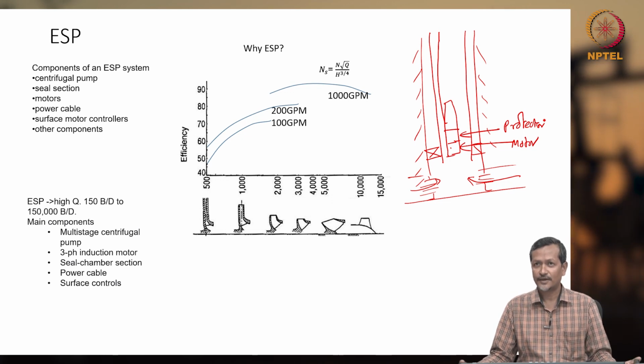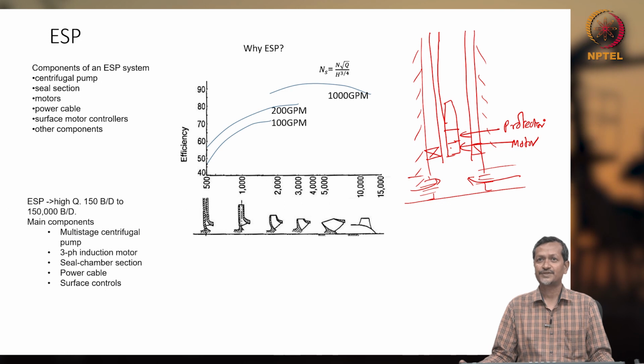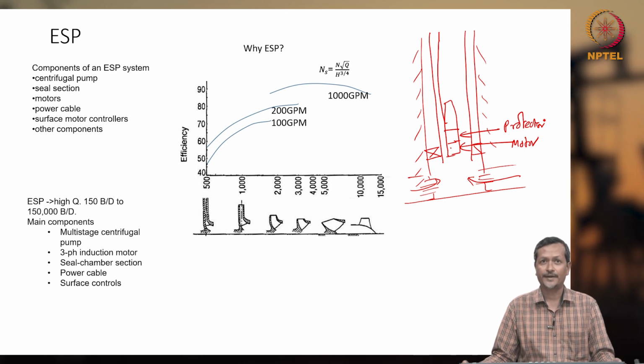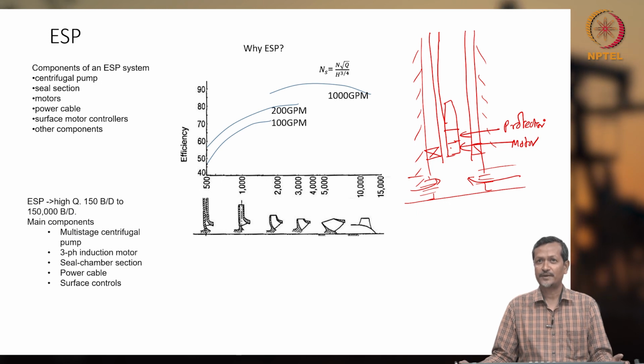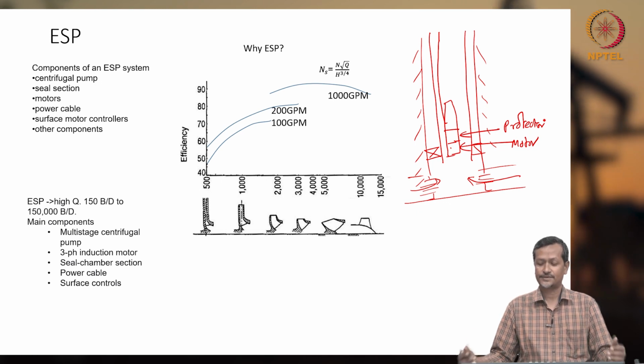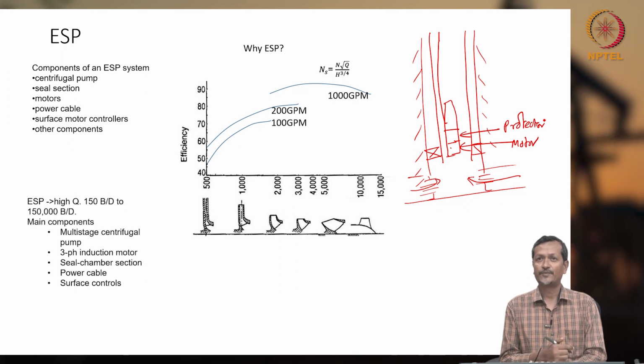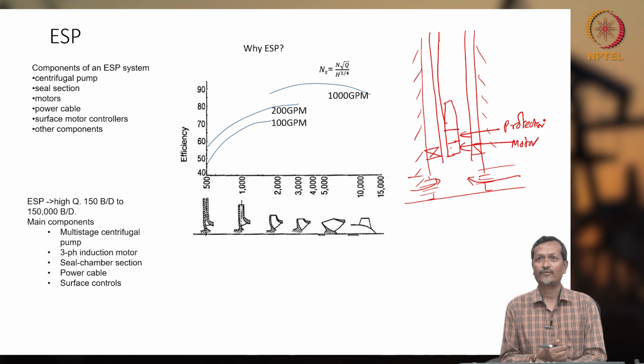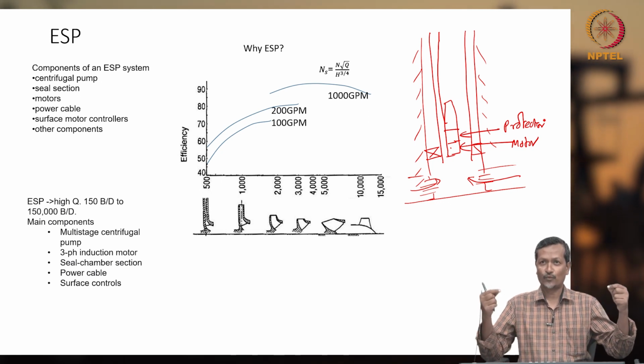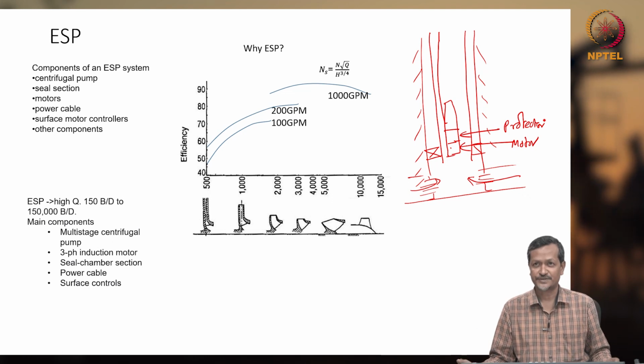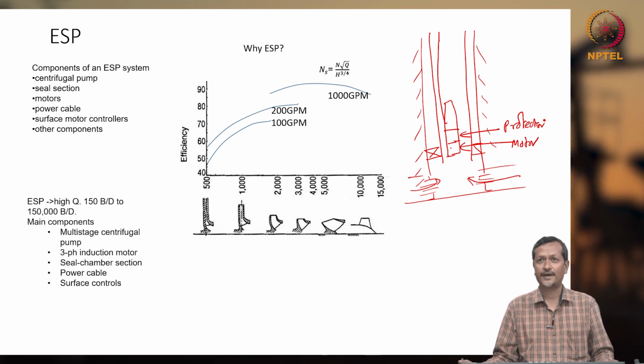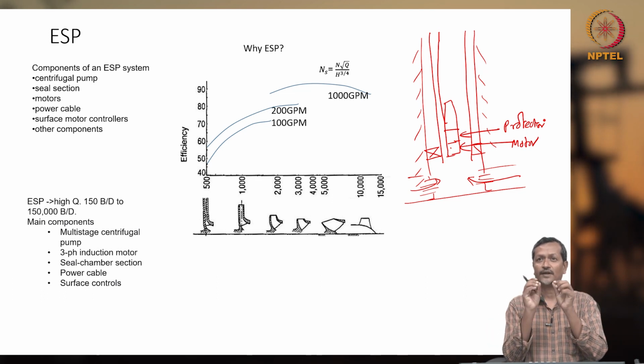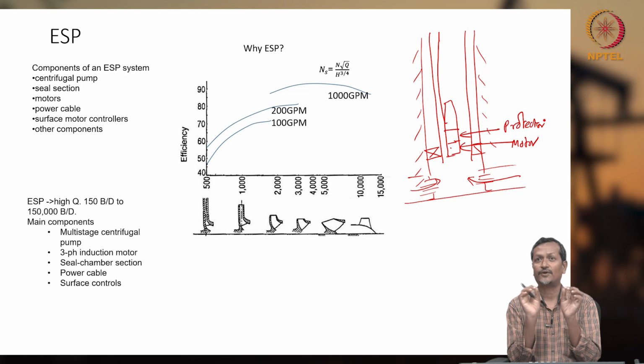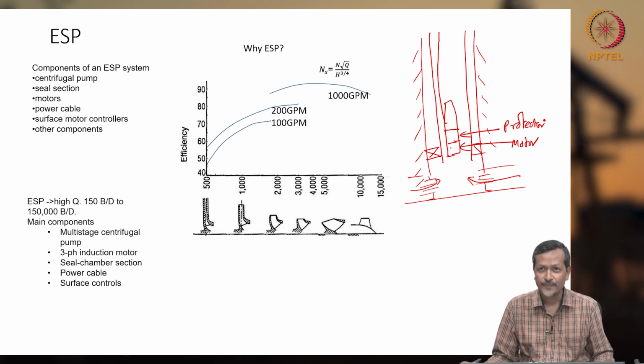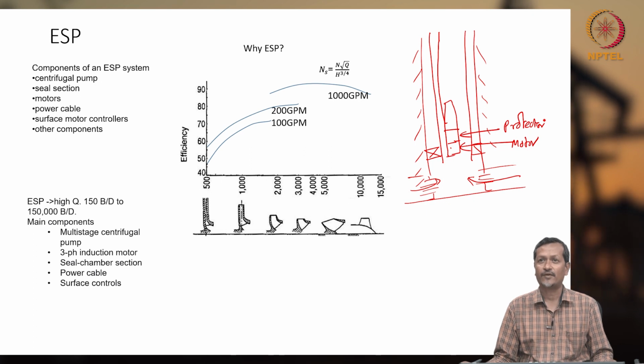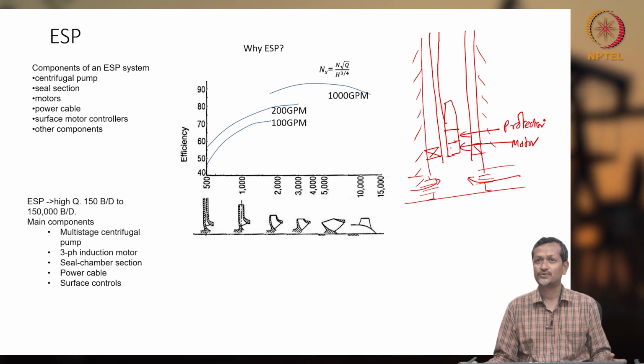The motor is an electrical unit, and if water or wellbore fluid enters your motor, then the motor coil will get burned. In normal application you don't want to burn it, because burning a motor under wellbore conditions means you have to remove the whole system. That will be an expensive affair. So you have to avoid injecting water inside the motor. Inside there will be transformer oil or motor oil, creating such an environment inside the motor that the coil and magnet will not touch each other, and it will not burn or create any spark. But if water enters, the dielectric fluid will create a problem. So you have to avoid injecting water by mistake also, through seal leakage or any other method.